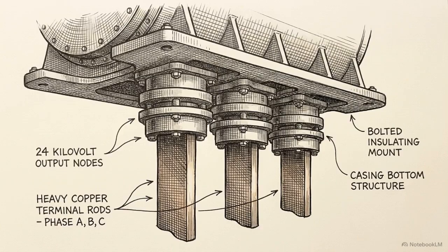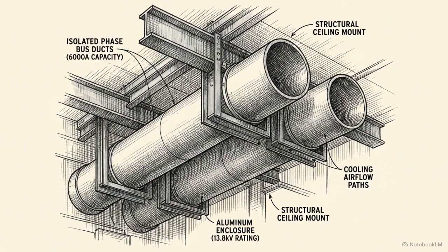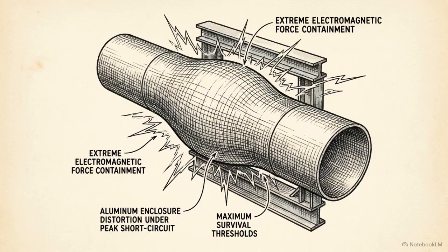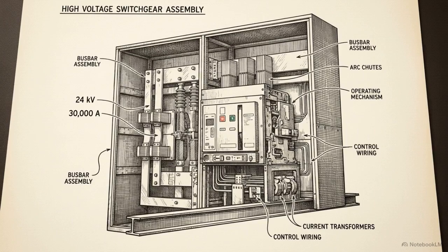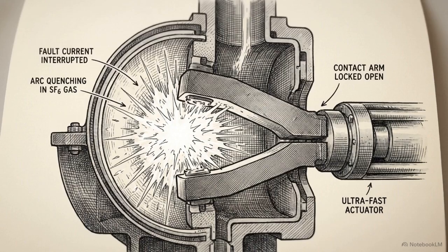Transporting this load requires isolated phase bus ducts built from thick aluminum. They are rated to carry 31,500 amps continuously and engineered to physically survive the violent electromagnetic forces of a 560 kiloamp peak short circuit. This schematic details the critical node between the generator and the 400 kilovolt grid, the GE FKGA8 generator circuit breaker. Using pressurized sulfur hexafluoride gas at 0.95 megapascals and a forced air cooling system, this breaker is capable of physically severing a massive 105 kiloamp fault current in exactly 75 milliseconds.